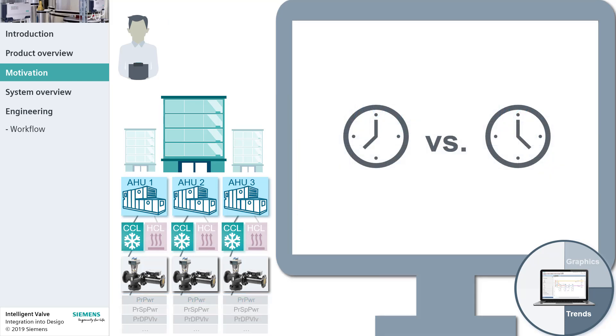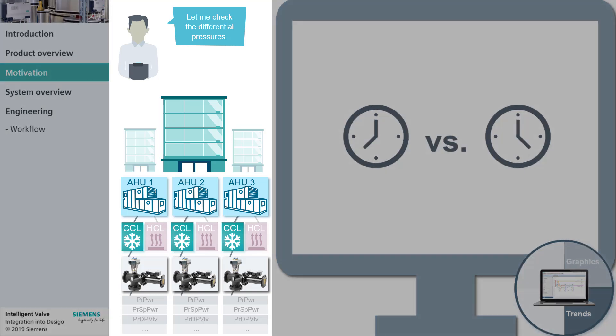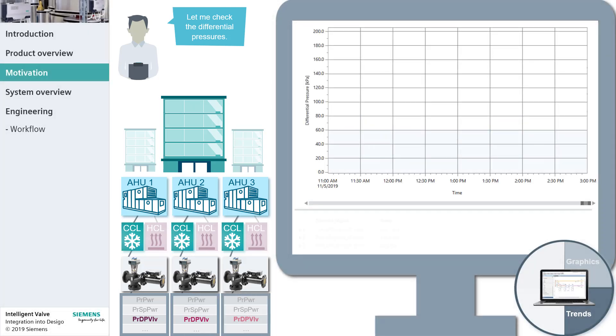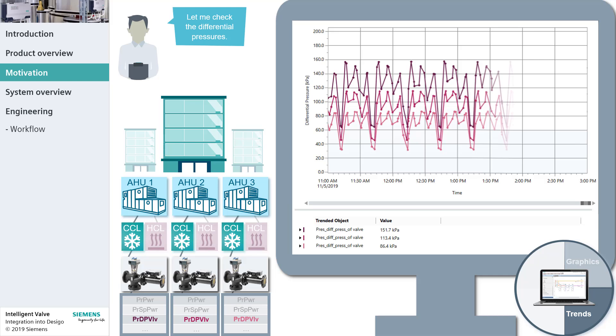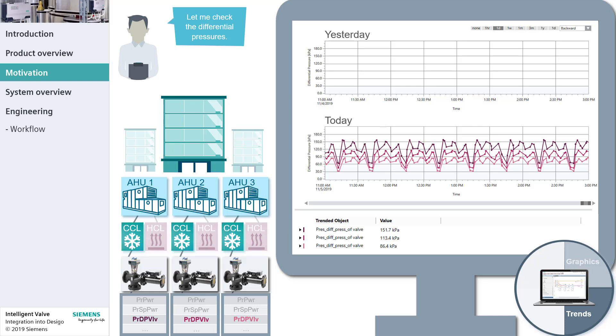The third option, time shift comparisons, allows Mike to make comparisons of trended historical and real-time data on different days for the same time period. Mike is interested in optimizing not only the thermal, but also the hydraulic power consumption. For this purpose, Mike checks the differential pressures across the intelligent valves. Today's values seem higher than usual, however he's not quite sure about it. Mike decides to conduct a time shift comparison with the current data in the trend below and the historical data in the trend above.